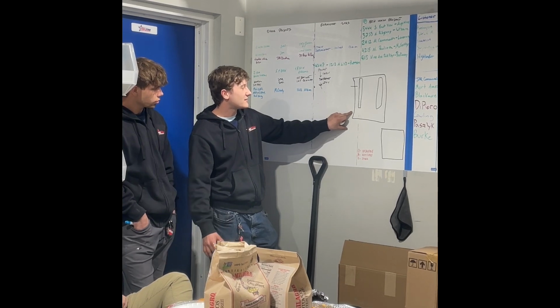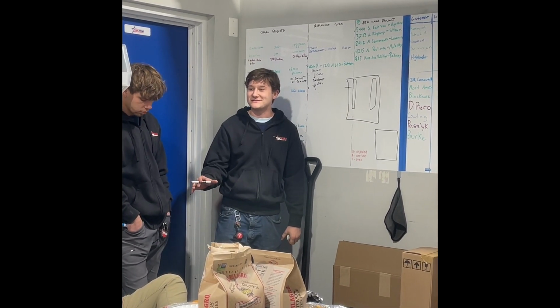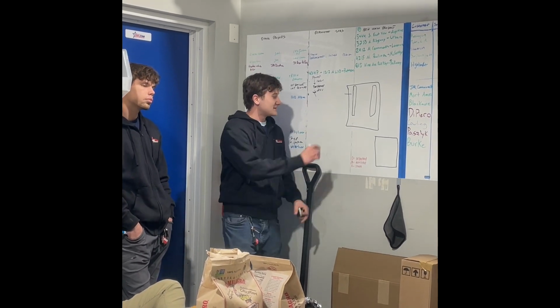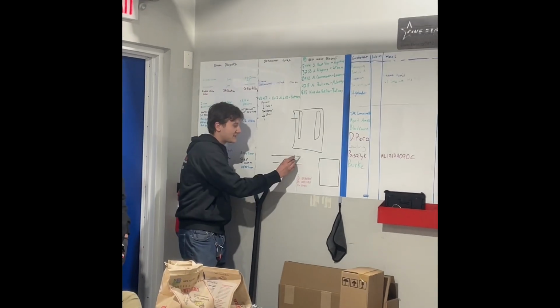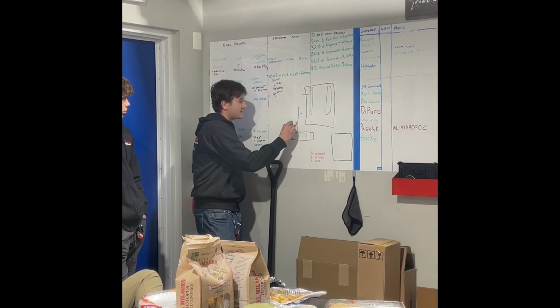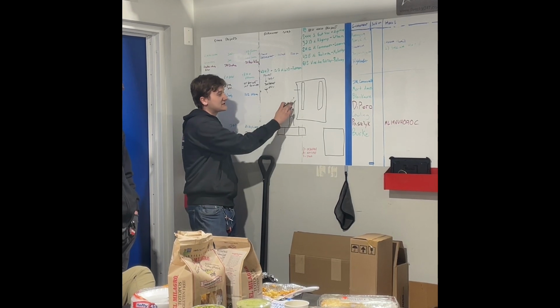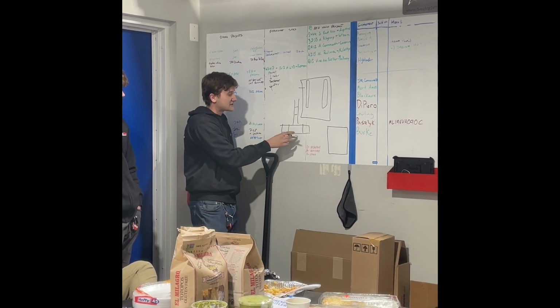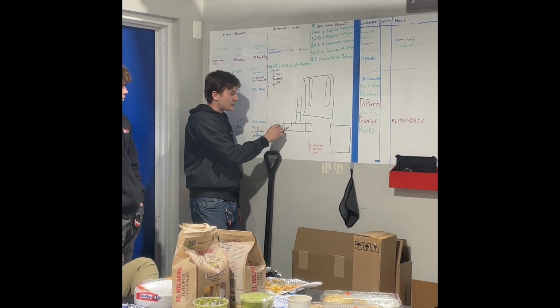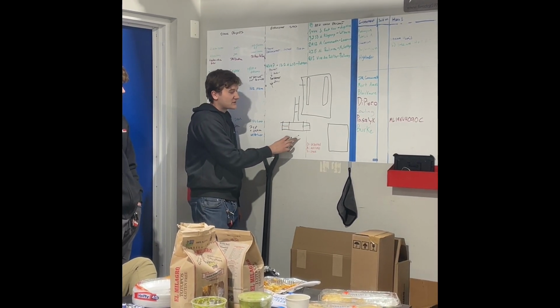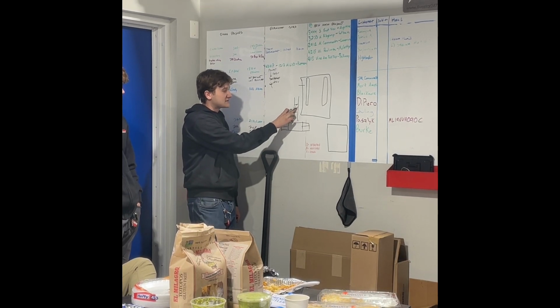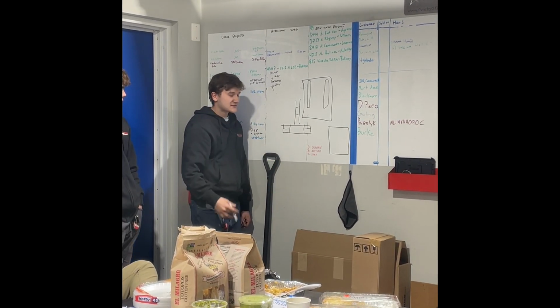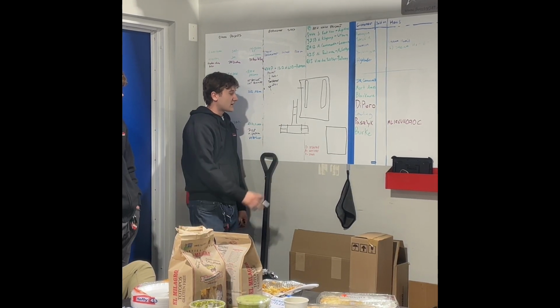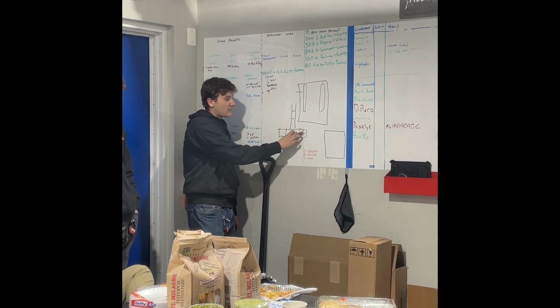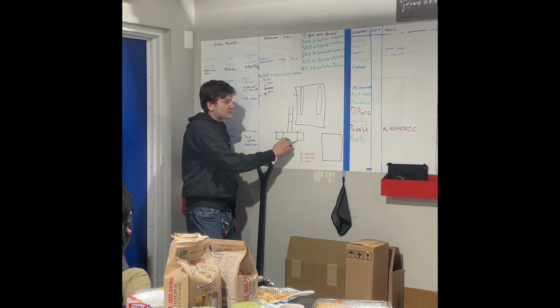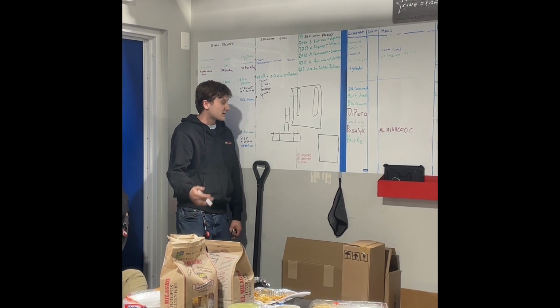And so when the customer turns on the thermostat in the master bedroom, here I'm gonna go back to the ductwork actually. Okay, so this is 1 damper, damper number 2, 3rd damper. So this is going to the customer's bedroom, and when the customer turned on the thermostat, let's say, these 2 are gonna close. They're normally open, so once power is sent to them, they're gonna close. No power is gonna be sent to this one. Then the fan is gonna kick on, and it's gonna go through there. If both the thermostats are on, no power is gonna be sent to the dampers. They're just gonna be steadily open. The fan is gonna be running.